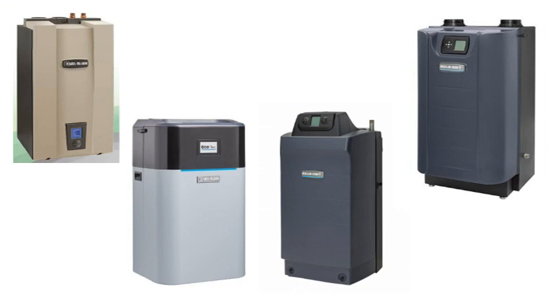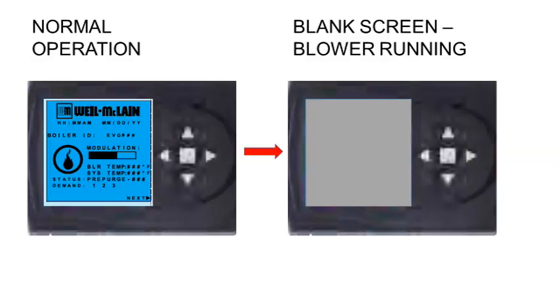I'm Brian, and today we will be taking a look at our condensing boilers that use the Ultra and Ecotech style control and what it means when the display is blank and the blower is running.